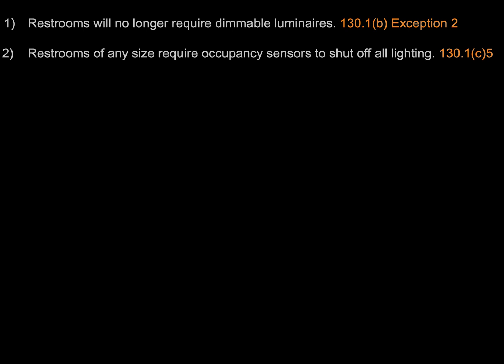My recommendation is to install ceiling mount sensors that are able to see all the motion within the restroom, so that they can look over any partitions that are installed, but they should not view outside of the restroom itself.